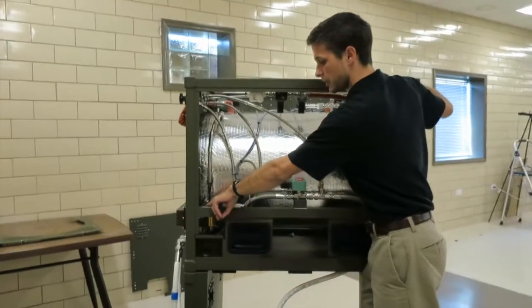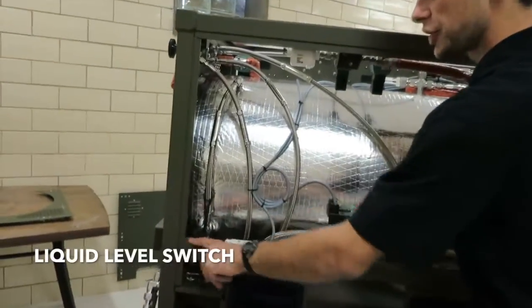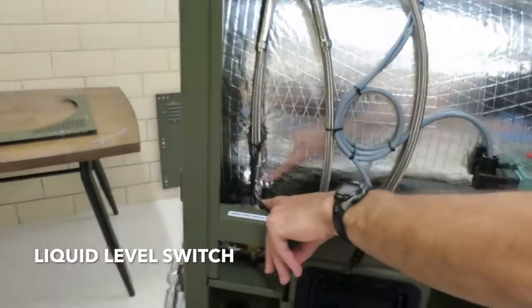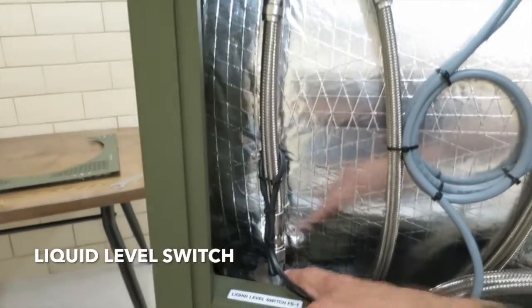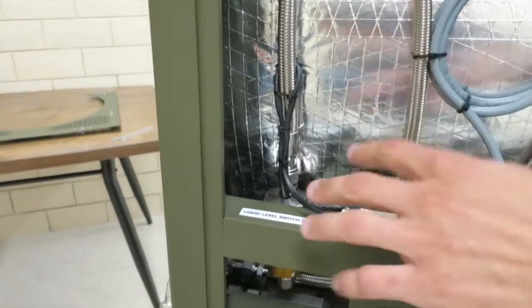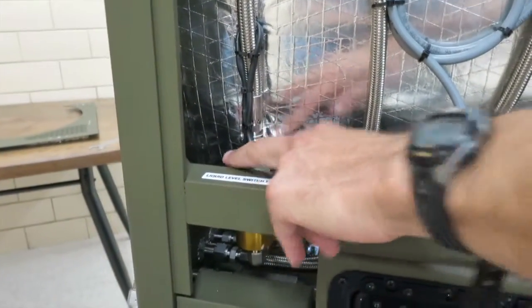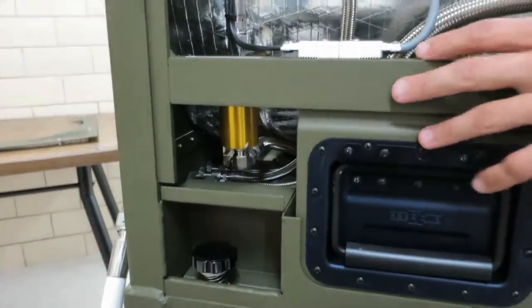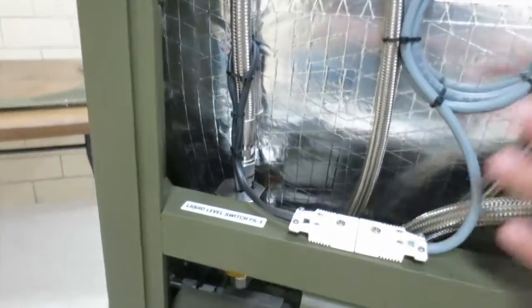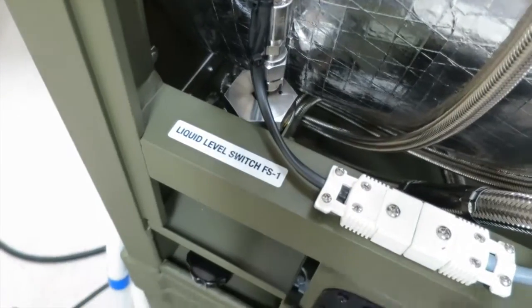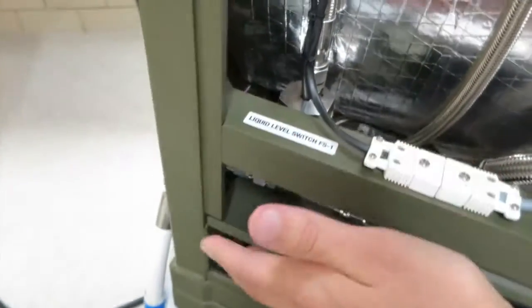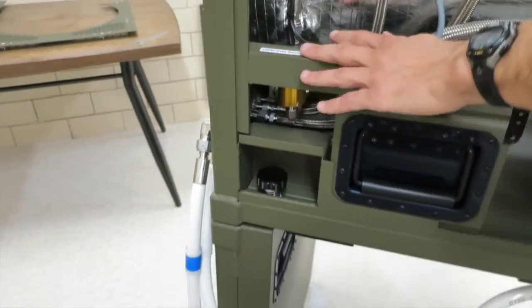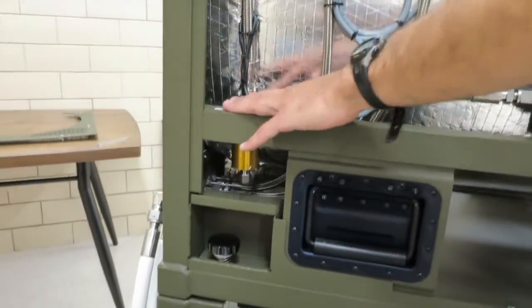So starting in the bottom left, we have the liquid level switch. What this does is it has a little float that is activated when you fill the jacket up with water. This liquid level switch tells the PLC whether there's water or not. If there's water, the PLC will operate as normal, turn on the heaters. If the jacket gets empty of water, it will not turn the heaters on. So this is going to protect you from overheating.